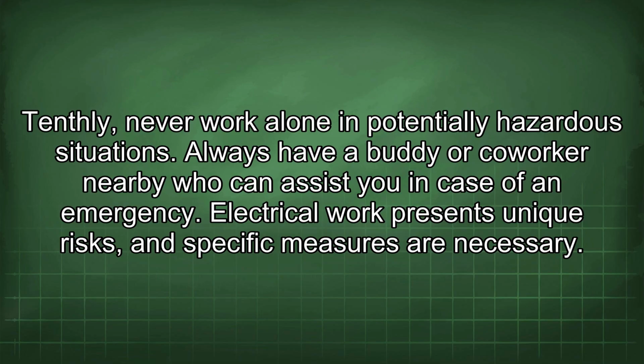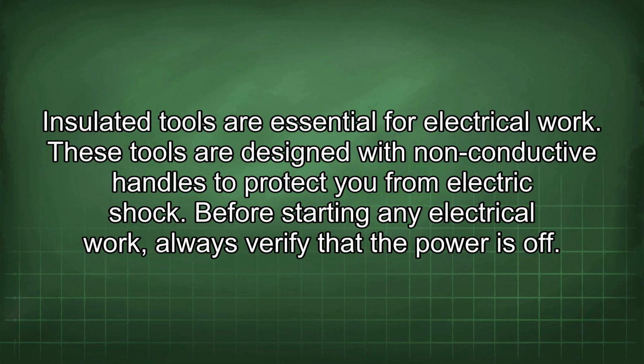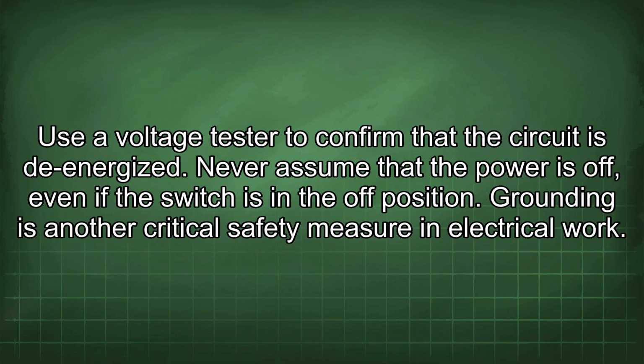Tenthly, never work alone in potentially hazardous situations. Always have a buddy or coworker nearby who can assist you in case of an emergency. Electrical work presents unique risks, and specific measures are necessary. Insulated tools are essential for electrical work. These tools are designed with non-conductive handles to protect you from electric shock. Before starting any electrical work, always verify that the power is off. Use a voltage tester to confirm that the circuit is de-energized. Never assume that the power is off, even if the switch is in the off position.